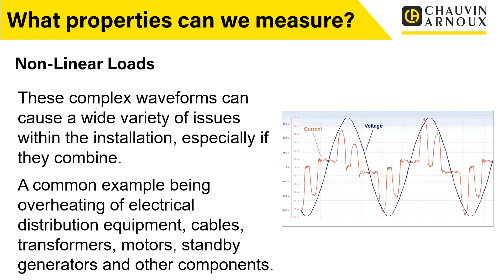Most distribution equipment isn't designed to deal with this sort of quick switching on and off, high frequency events going on - they're designed for steady, normal linear loads. So when we introduce nonlinear loads, and as a result, what I'll talk about in a moment, harmonics, that can have detrimental effects on the electrical installation.